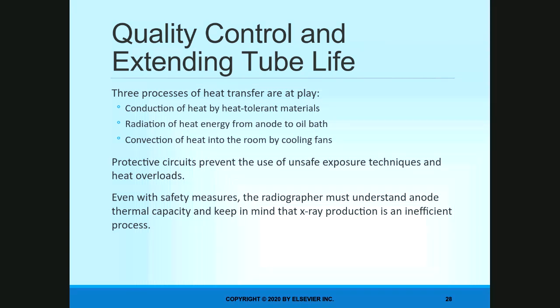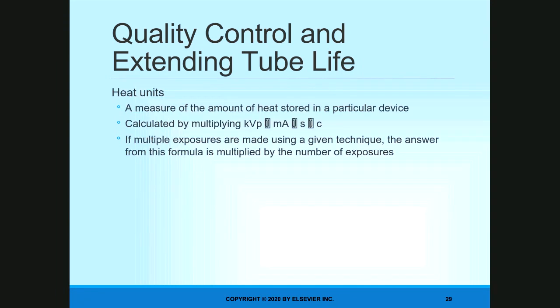Even with that said, though, we have to understand that X-ray is still very inefficient. 99% of what we create is heat, and only 1% is radiation. So we have to be mindful of that when we choose our technical values and think about what we're asking the machine to do.